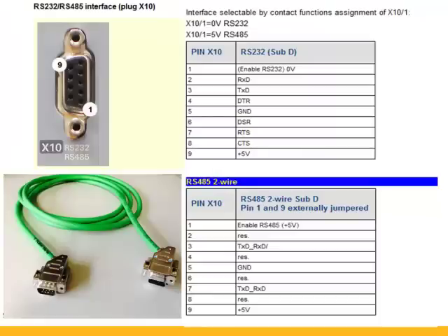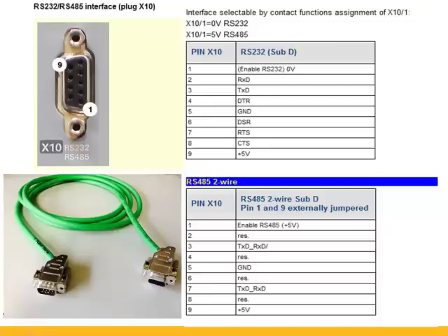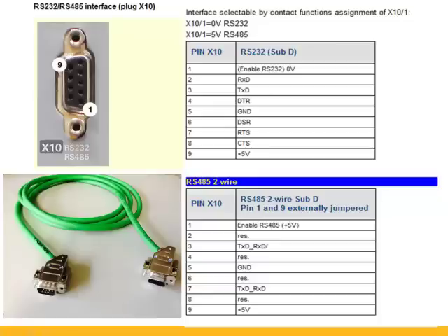On the RS-232 and 485 interface on the Compax 3, that uses the green serial SSK1-02 cable. You'll notice in the documentation, pin number 1 needs to be 0 volts on power up for RS-232. If pin number 1 is connected to anything, it will come up in 485 mode and you won't be able to connect through your PC. You'll notice that pin number 1 on RS-232 is not populated at all for this reason.